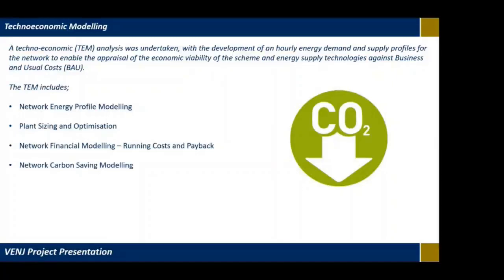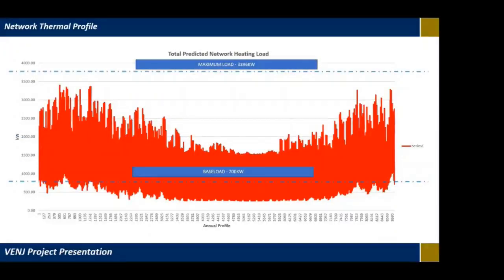Network financial modelling, running costs and payback, and network carbon savings modelling were all done. In terms of the actual predicted total load profile, the maximum load of the network is just under 4 megawatts. The base load is about 700, and that's why we've selected the water source heat pump to be sized on that base load, so it runs primarily all year and is topped up by the CHP and boilers at the shoulder and peak winter periods. So the aim is to maximise the heat pump operation.